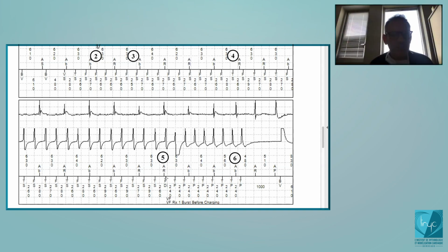And once more, this is not something that you can readapt, reprogram, or deprogram. If you program 2 zones, VT and VF, it is going to be systematically on and you cannot deprogram it. Okay, any question? No, it's clear for everybody.